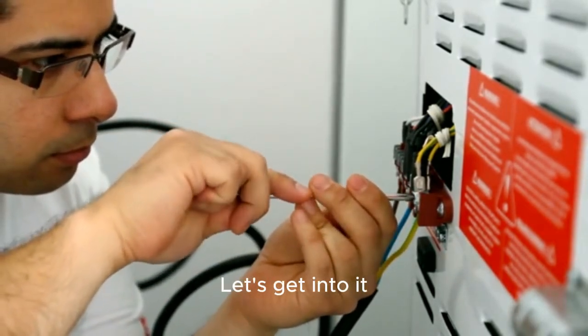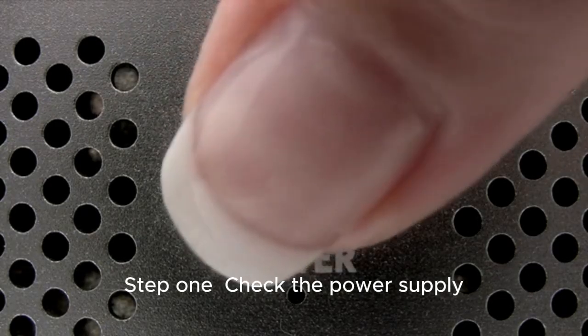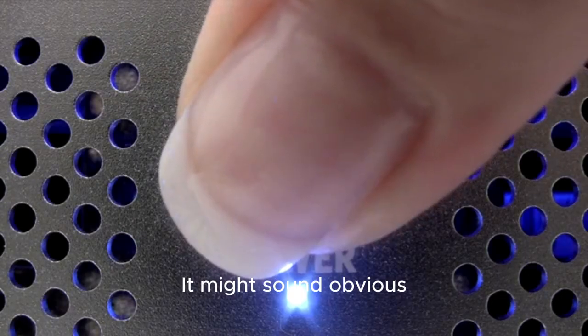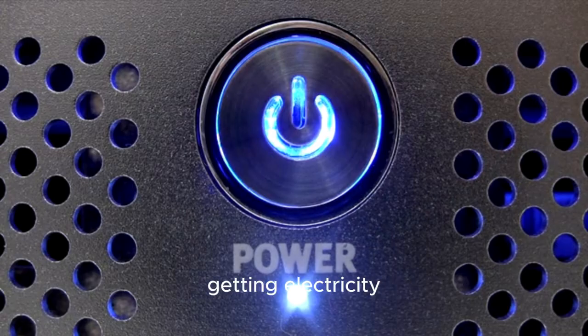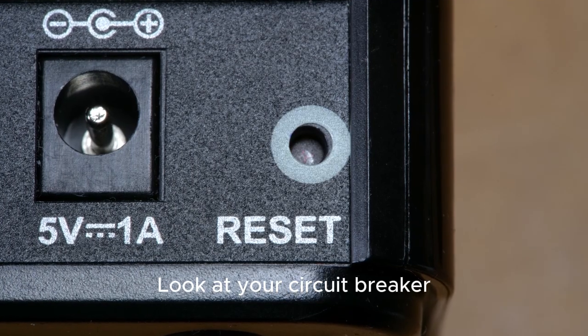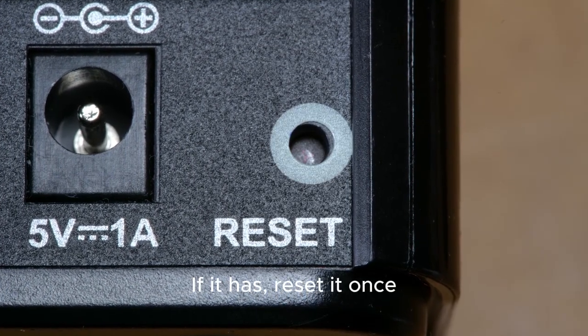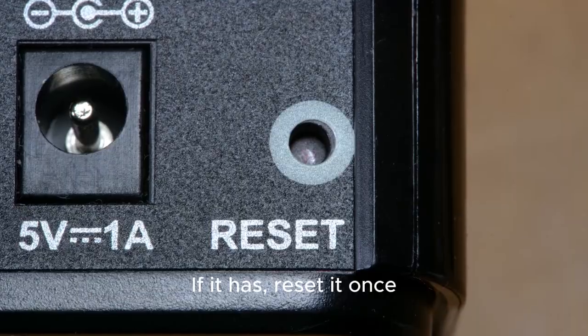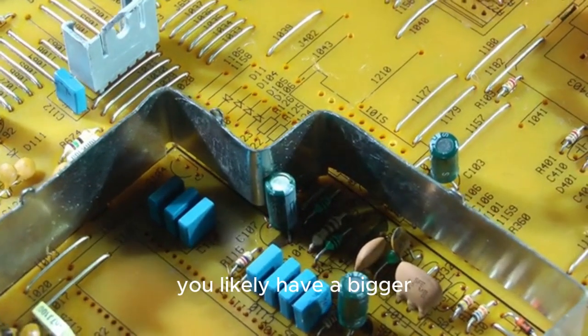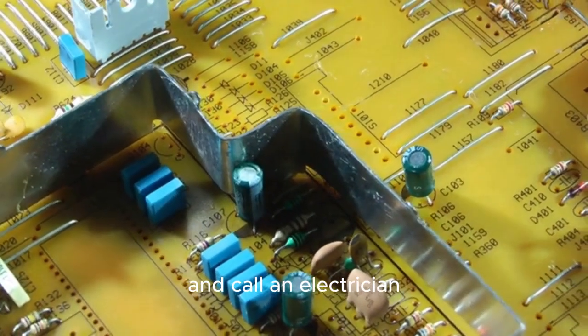Let's get into it. Step 1. Check the power supply. It might sound obvious, but make sure the boiler is actually getting electricity. Look at your circuit breaker and see if it has tripped. If it has, reset it once. If it trips again, you likely have a bigger issue and should stop here and call an electrician.